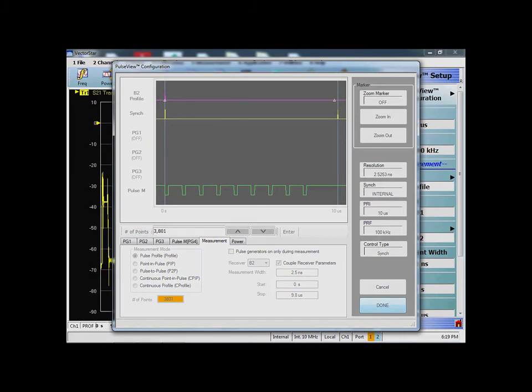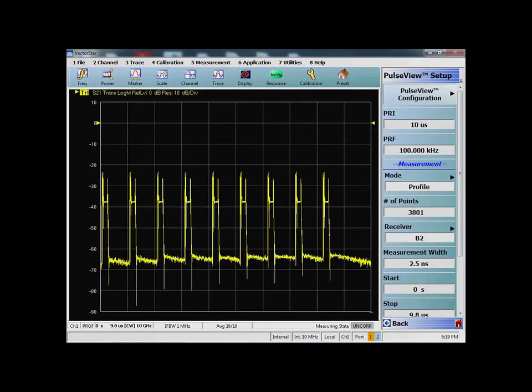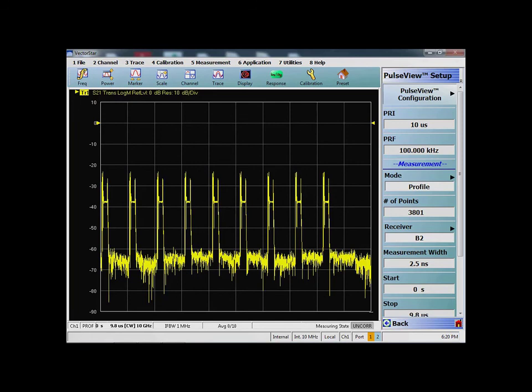Now it's going to take some time in processing, because for each and every pulse it's trying to process the data. This graph that you're seeing right now was done before, but whenever an update happens, that is the time you will be able to see the pulses as is. So this display right now is frozen. It's an older display because I was doing some settings, but you will see now this one has updated. So this is the first of the averaging. That means now you can actually see 9 pulses with the overshoots, the ringing, and the entire pulse in a complete manner.